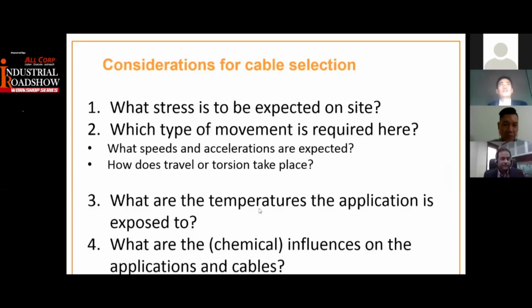Probably you're looking at indoor or outdoor use, maybe a chiller room, very cold, minus 20 degrees, and all these questions have to be asked and thought about. Last but not least, a very interesting point many people fail to remember or understand: what chemical influences will you have on the cables used on the equipment? Probably there's constant usage of oil, or some chemical in the air that causes the cables to start to crack up. So these are the 4 things you need to consider for cable selections.